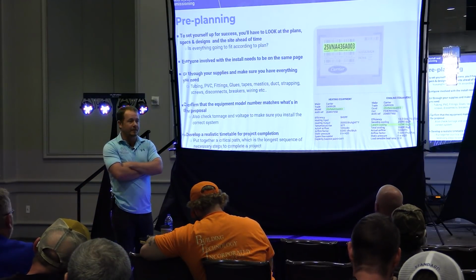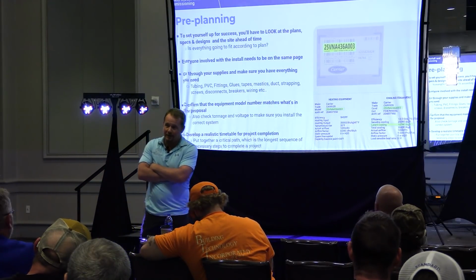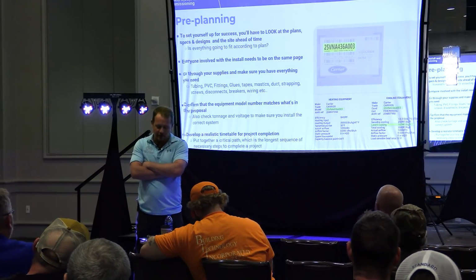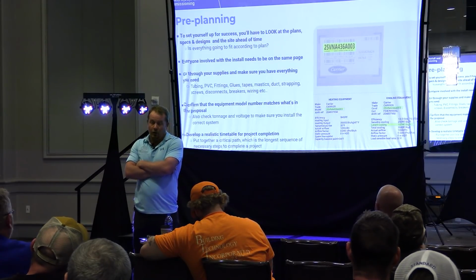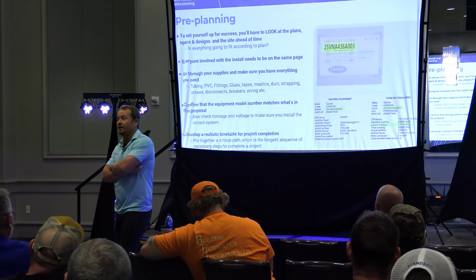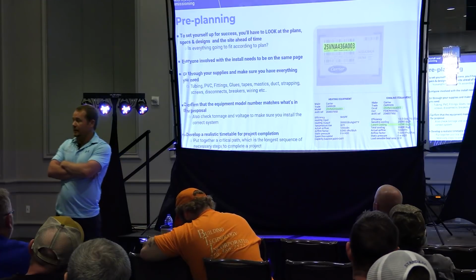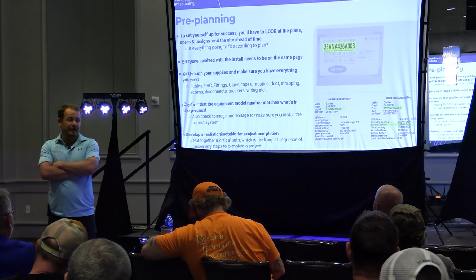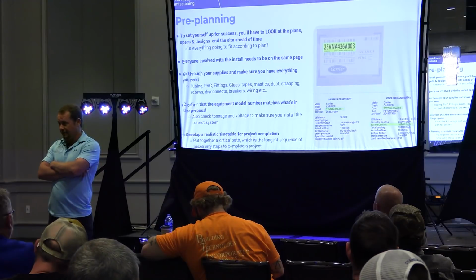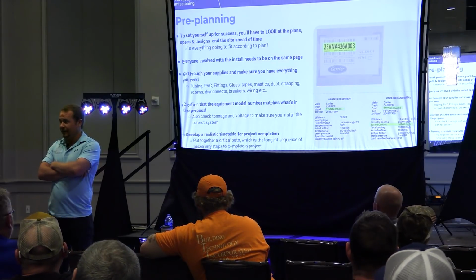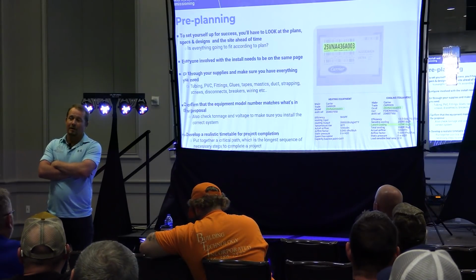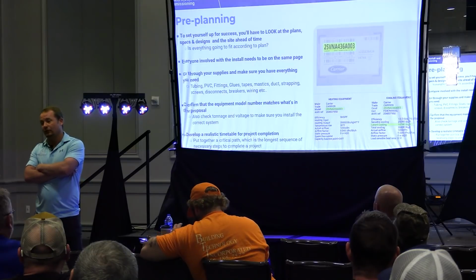is a dirty little secret, because the manufacturers will say this is getting better. This isn't always true, but for a long time they would say these systems dehumidify amazingly. Look at the statistics on them, they dehumidify so well. That's true when they're at full speed. But when they stage down, yeah, they run longer, but the sensible heat ratio starts creeping up.